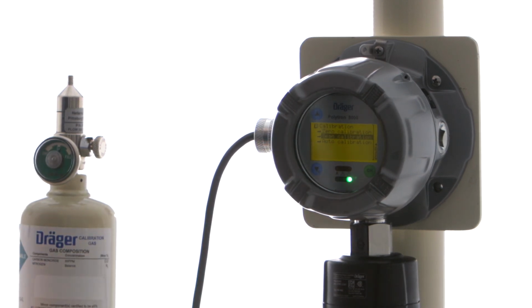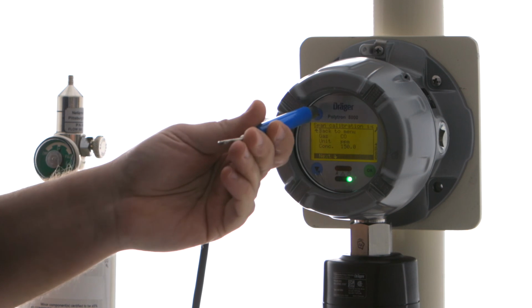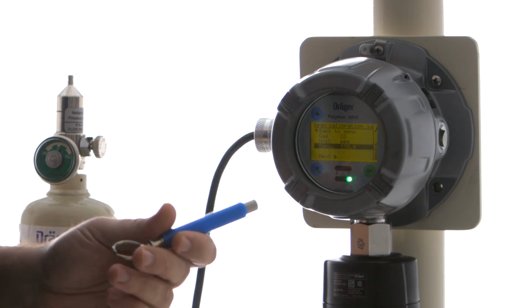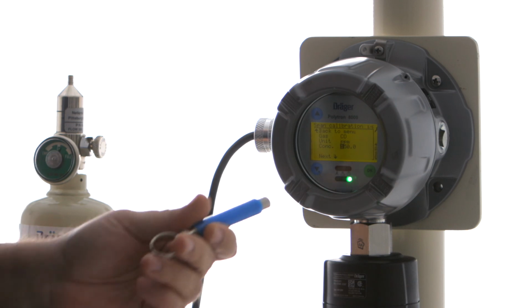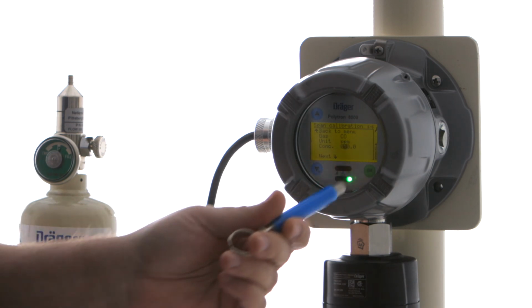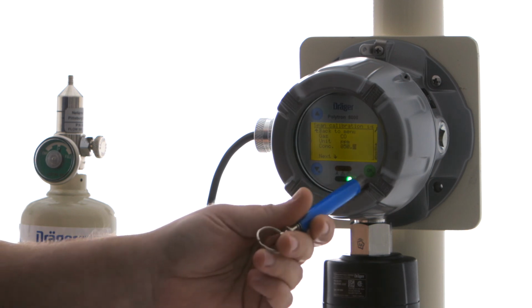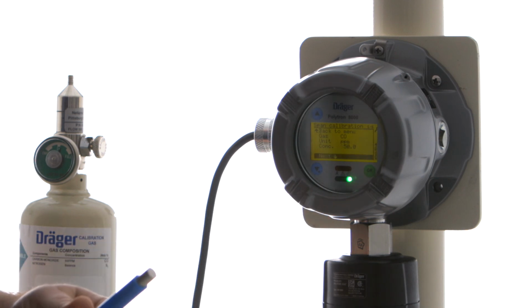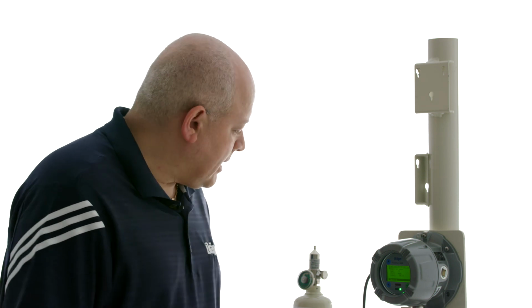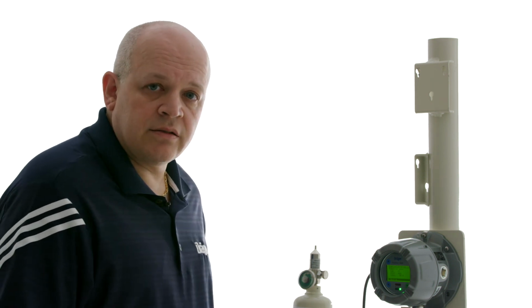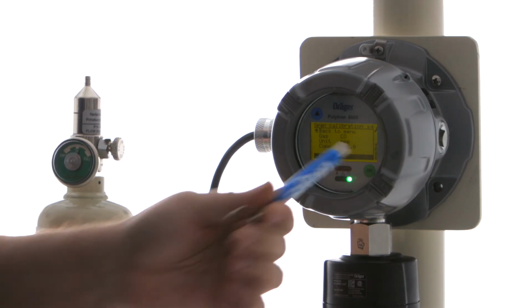We're going to go to span calibration, and again we're going to calibrate with a 50 ppm cylinder of carbon monoxide. Here is where you can choose what span gas concentration you're actually going to use and what type of span gas you're going to use. So if we select the up arrow until our concentration is selected, we're going to put in 50 ppm. So now we have CO, our unit of measure is ppm, and we have a 50 ppm concentration, and that concentration is going to be found on the cylinder that you're going to be using. So we're going to select next.